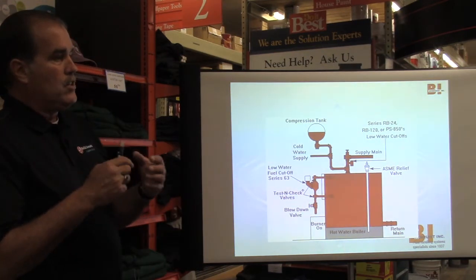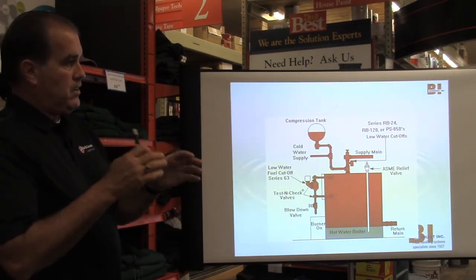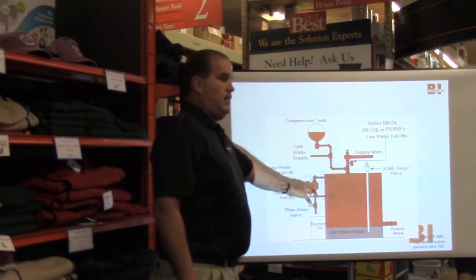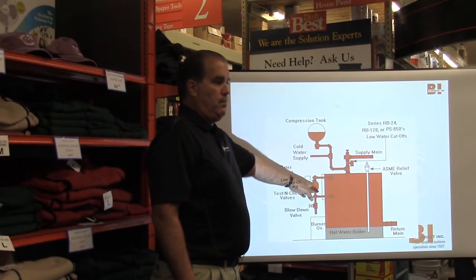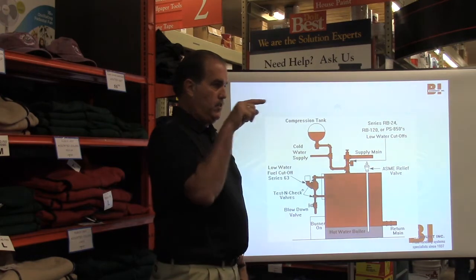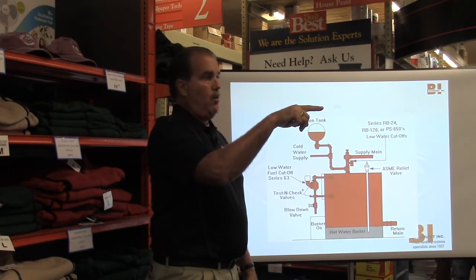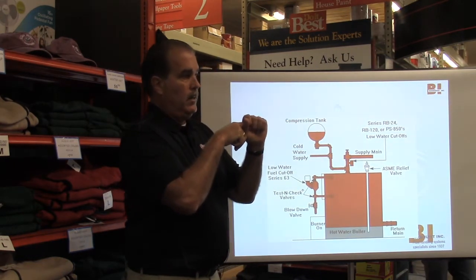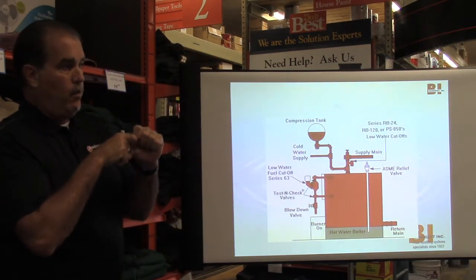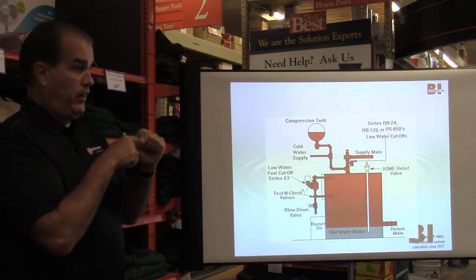Now, unfortunately, on most residential systems, you're probably not going to see one of these. You're going to see a probe type low water cutoff, which is just a single probe that goes into the water, and it's touching the water, and it uses the conductivity of water to know that it's in water.